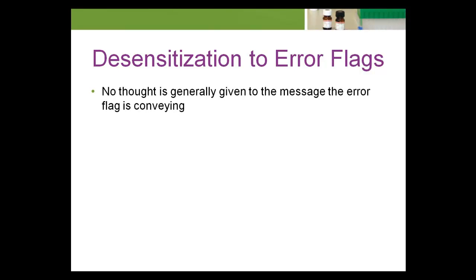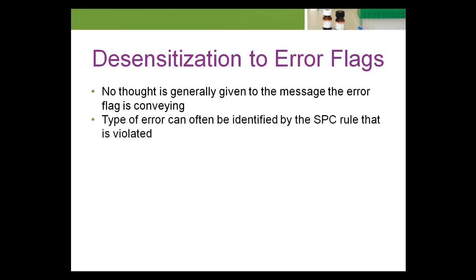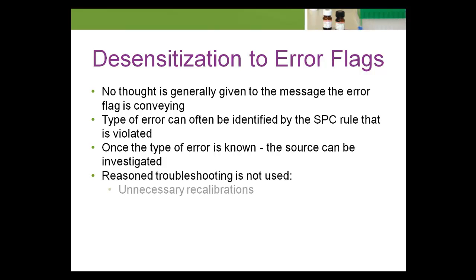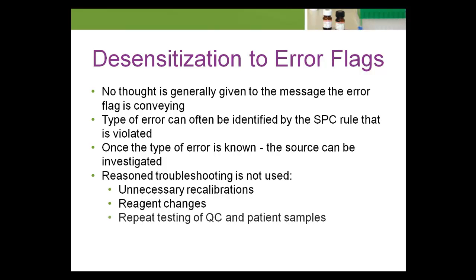When reasoned troubleshooting does not occur, no thought is generally given to the message the error flag is conveying. The type of error — random or systematic — can often be identified by the statistical process control rule that's violated. Once the type of error is known, then the source of the error can be investigated. When reasoned troubleshooting is not used, the results can be unnecessary recalibrations, reagent changes, and repeat testing of QC and patient samples, all of which equate to dollars wasted by the laboratory.